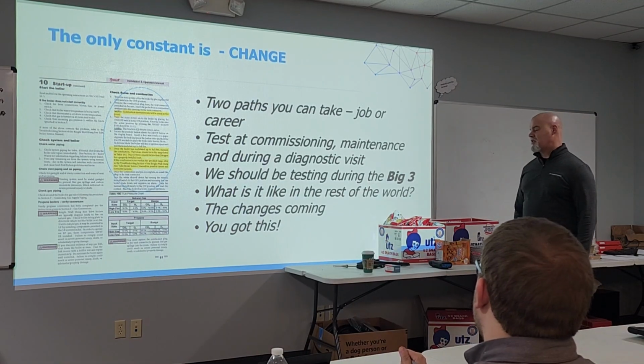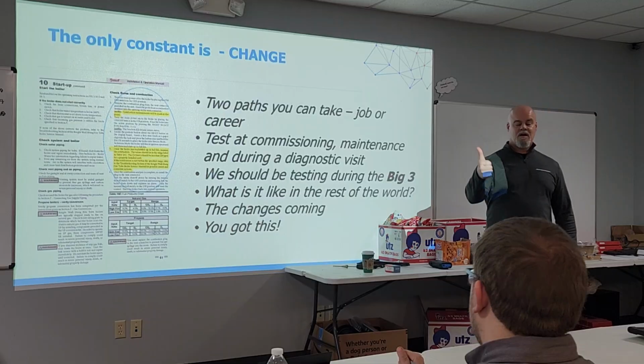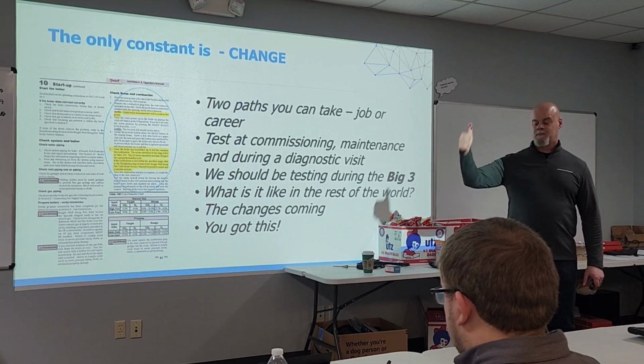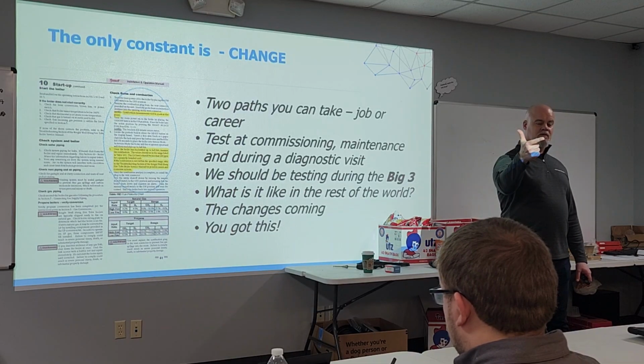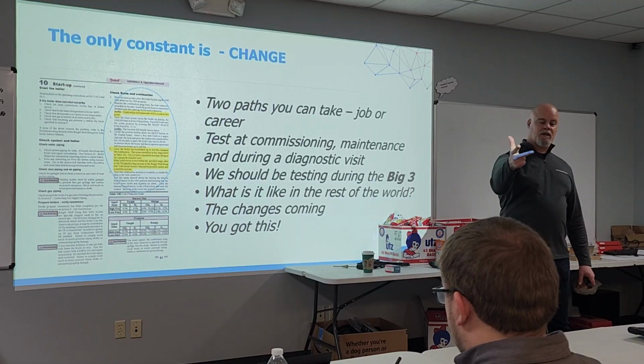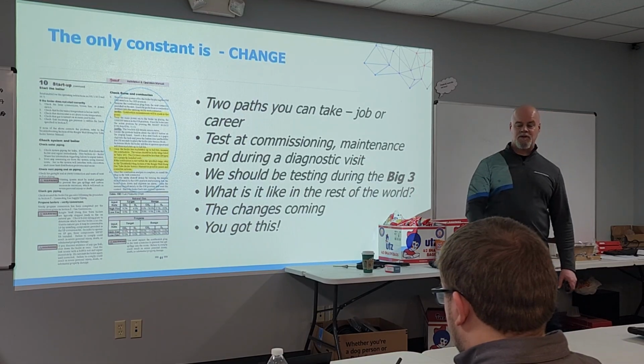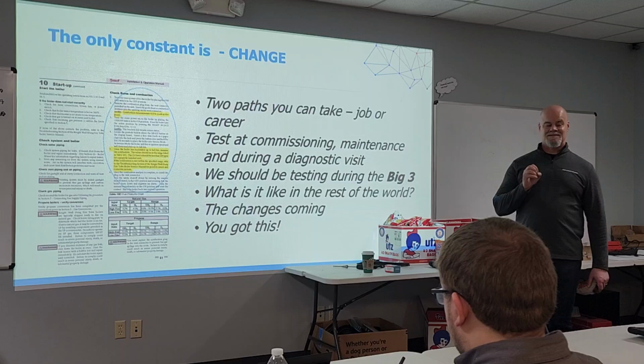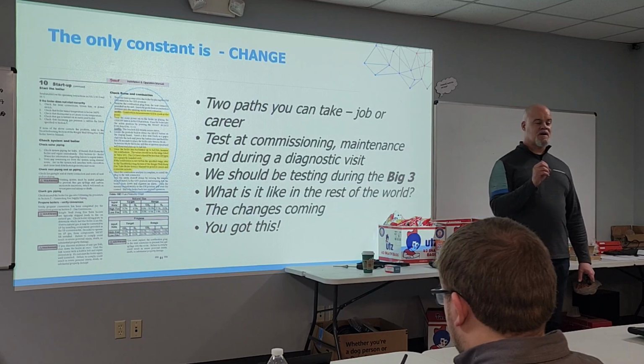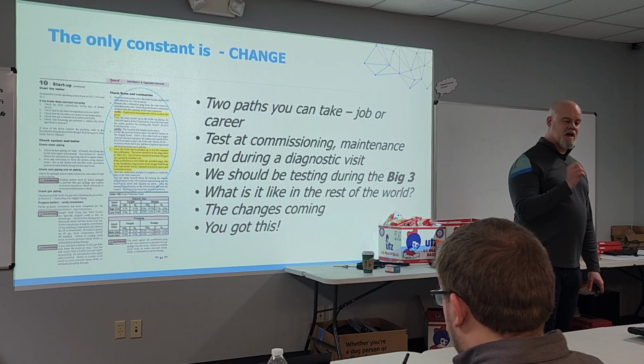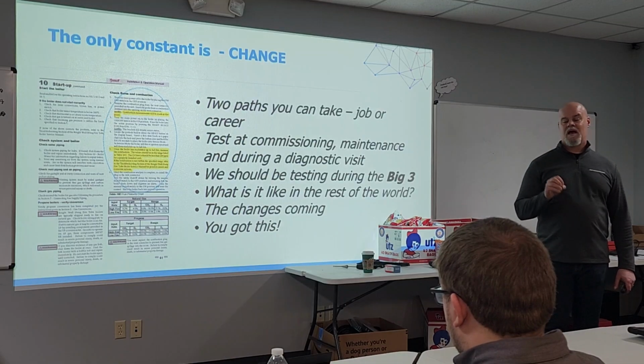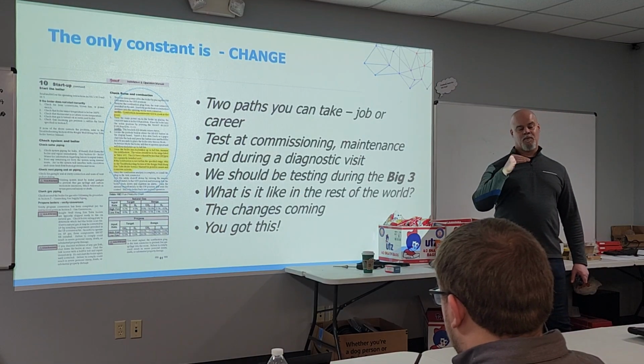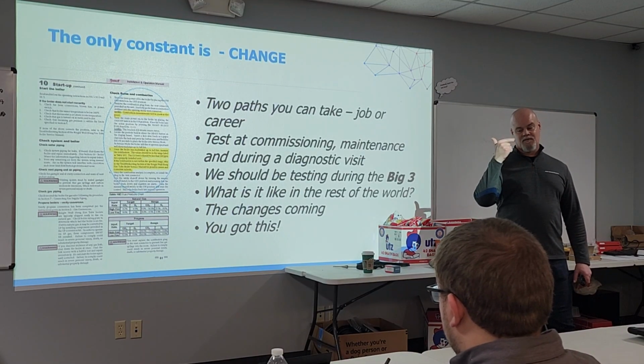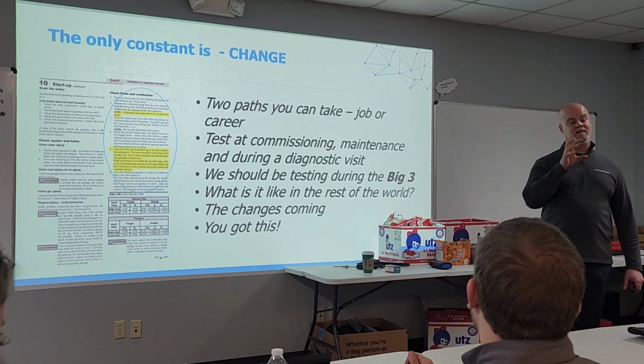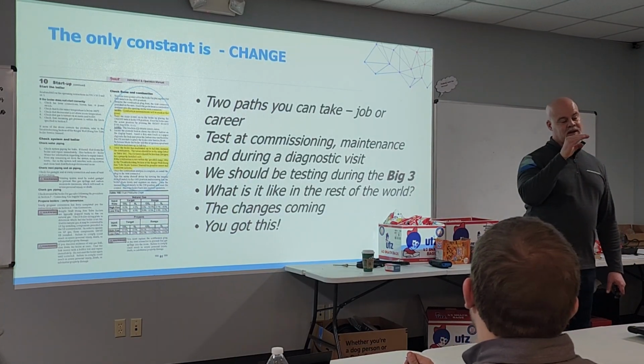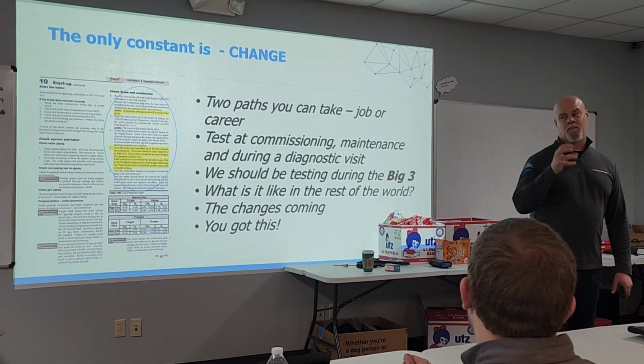We should be testing during the big three. What are the big three? Light off, the first 60 seconds of burner operation. Steady state, 5 minutes or greater of system runtime. Shutdown, 60 seconds after the burner shuts off. Why are we doing that? There are unique diagnostic characteristics, signatures, or behaviors that show themselves at each of those different operational rates or time periods: light off, steady state, shutdown. You can then diagnose the issues happening in each of those time periods and know what parts are impacting that.